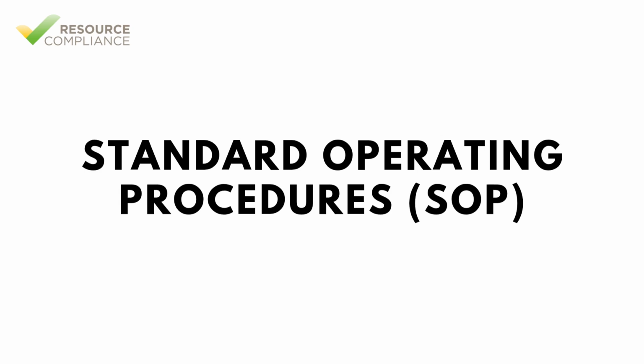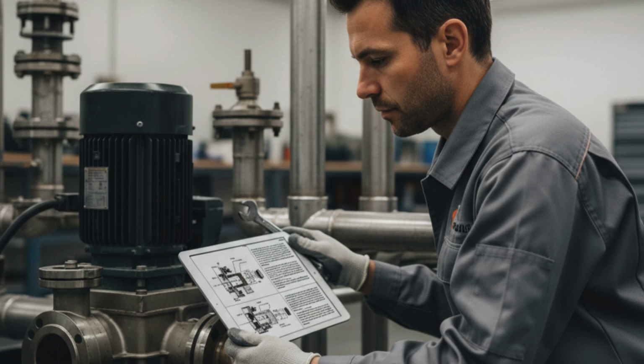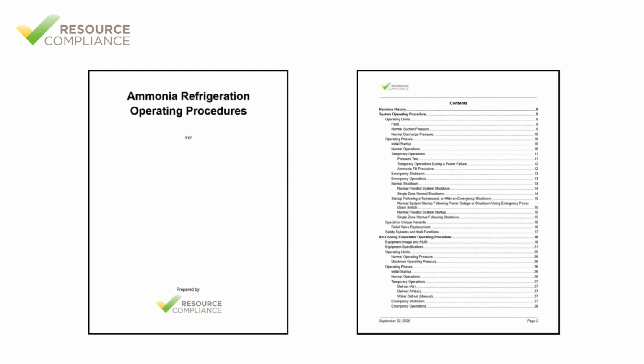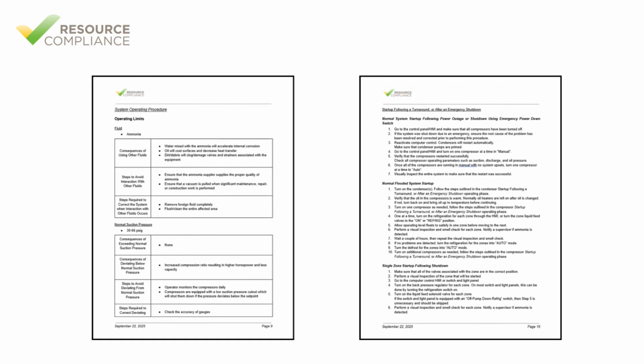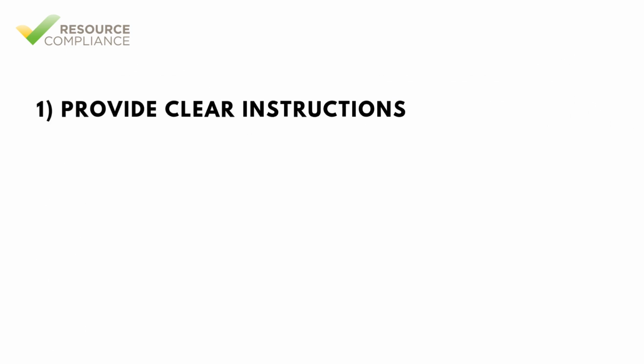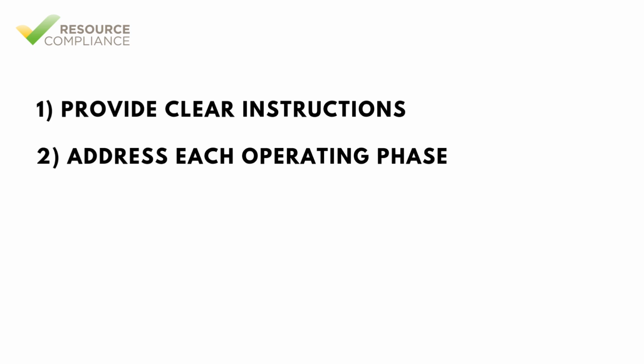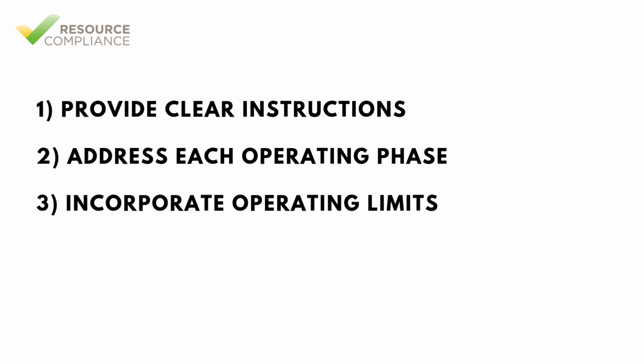Operating procedures, often called SOPs, are intended to provide site-specific instructions for the operator's routine tasks such as starting, stopping, and monitoring equipment. The RMP and PSM regulations lay out the prescriptive requirements for SOPs. SOPs must provide clear instruction for operating the ammonia refrigeration system, address each operating phase such as startup, shutdown, normal operations, and emergency operations, incorporate equipment operating limits, consequences of deviation, and steps to correct or avoid deviation.